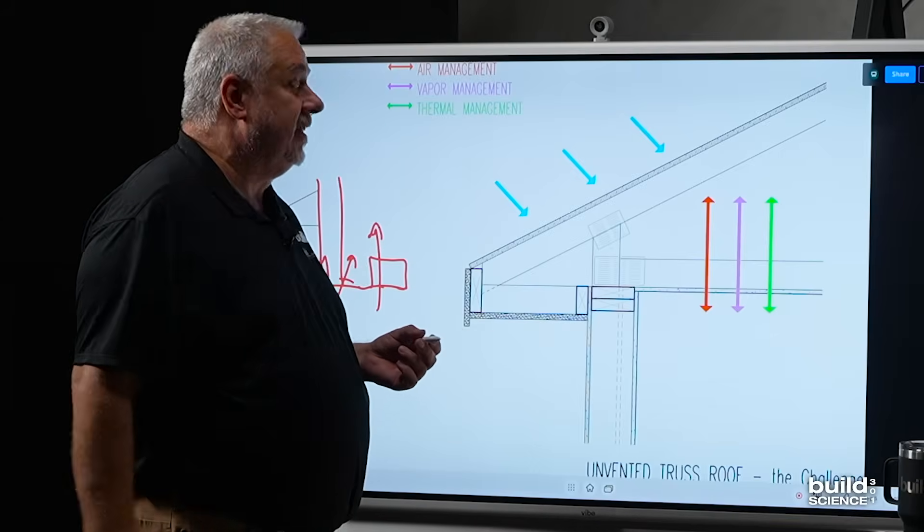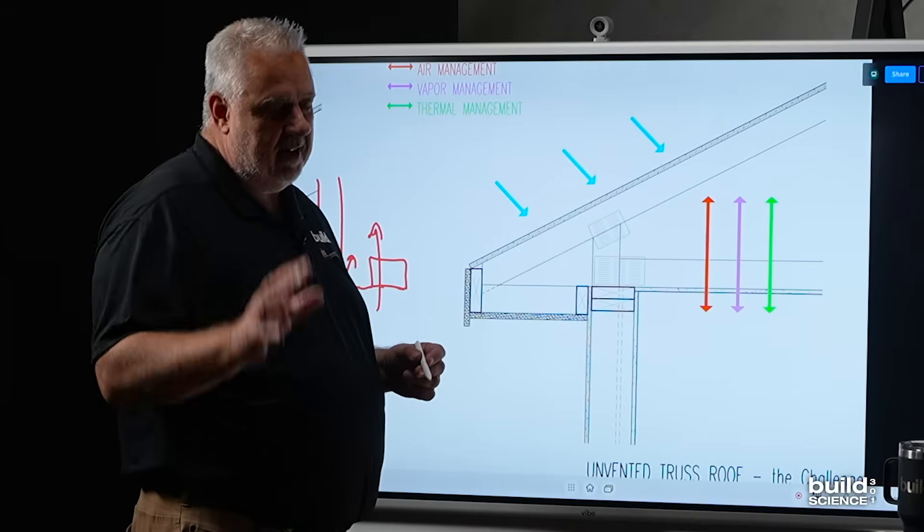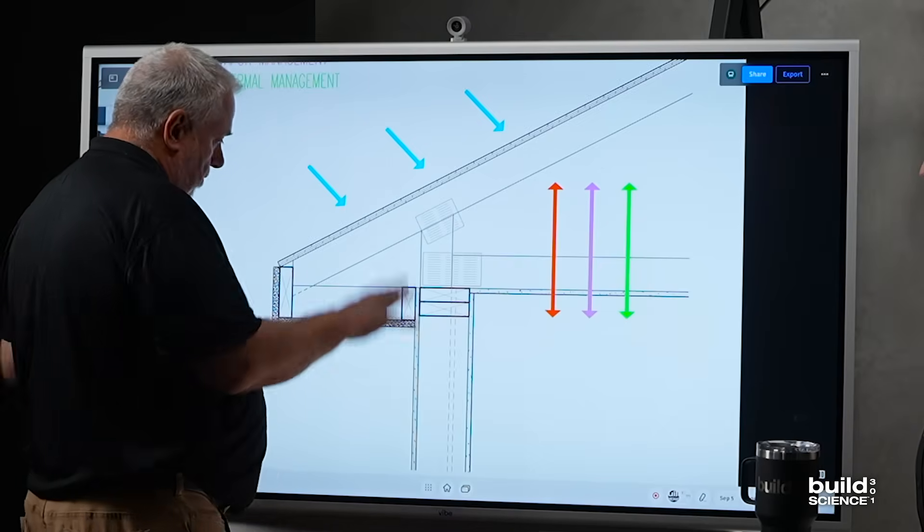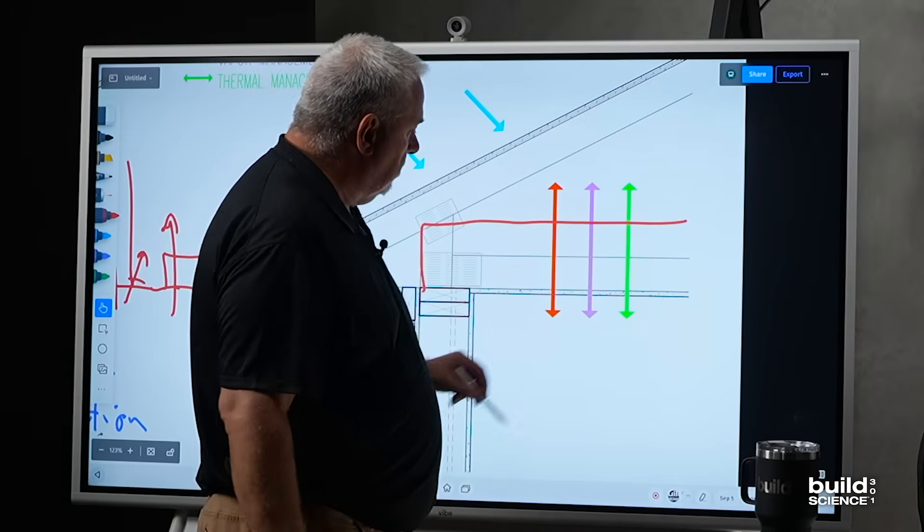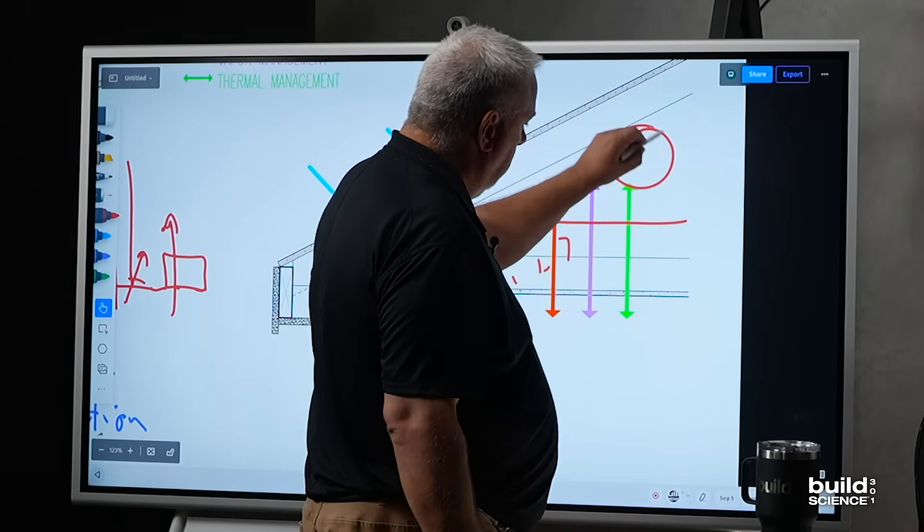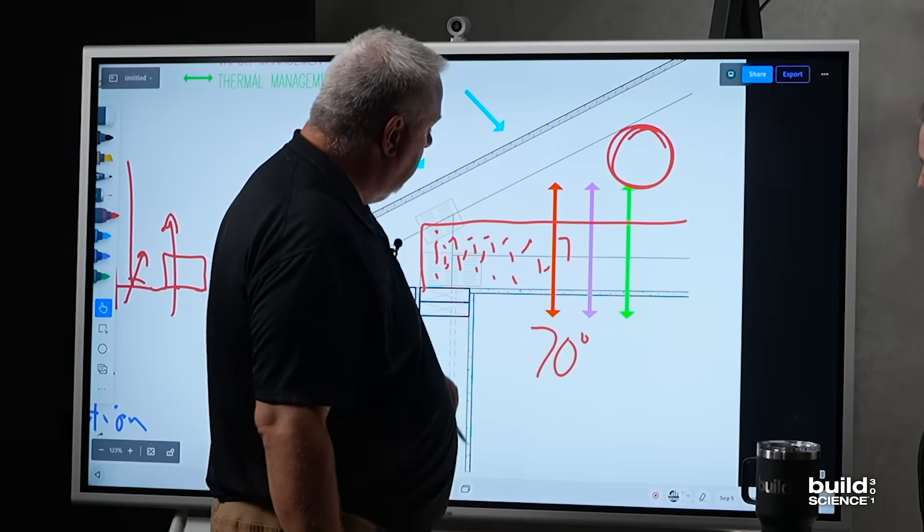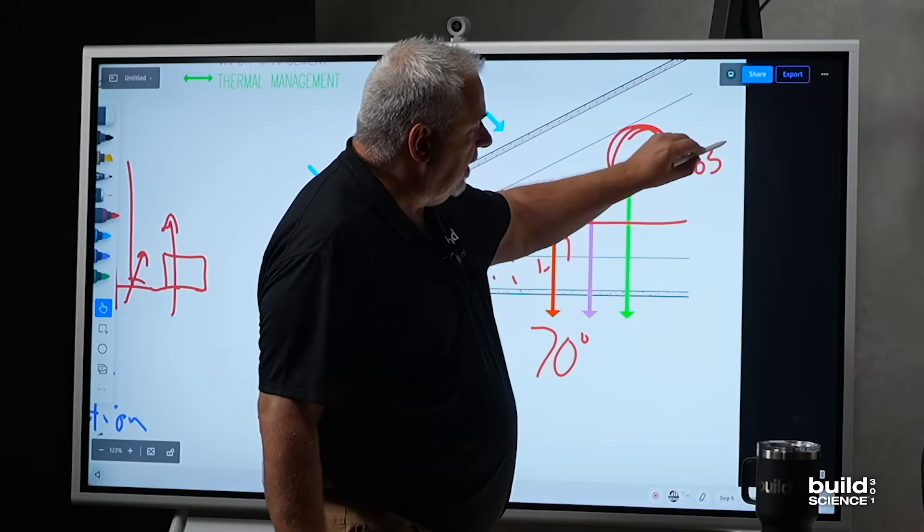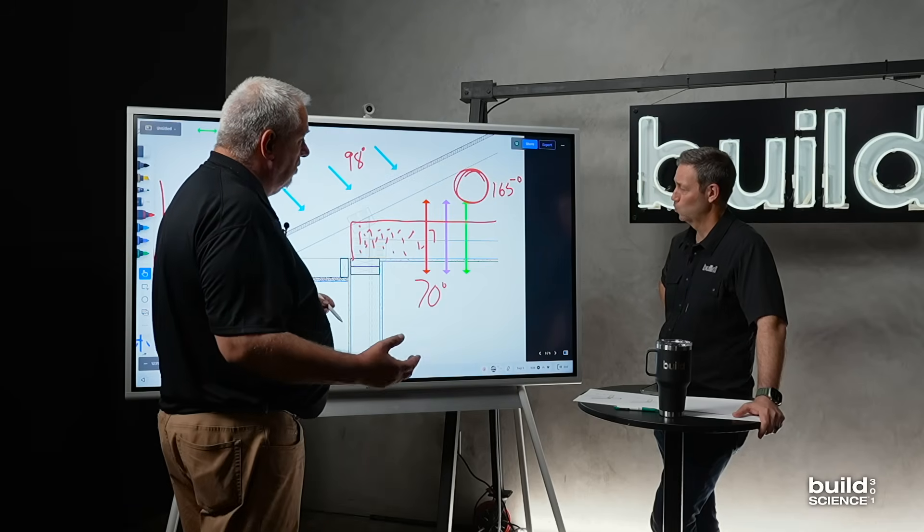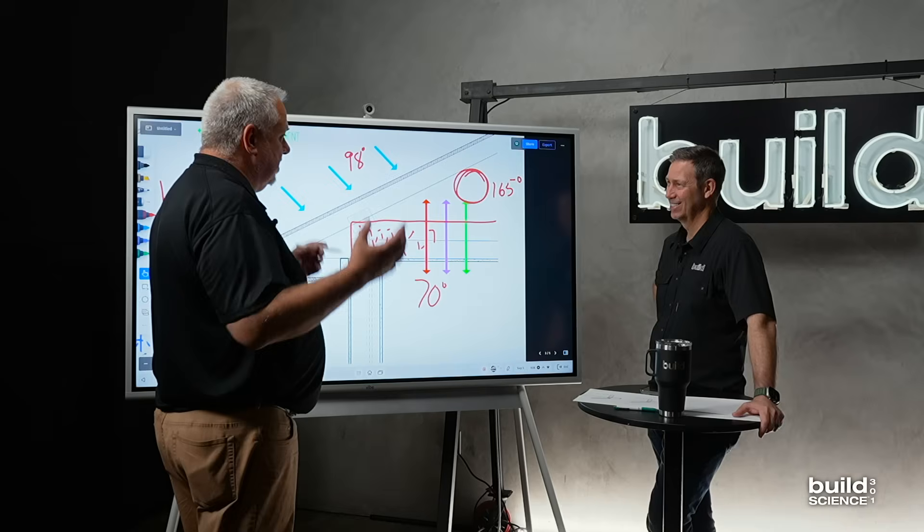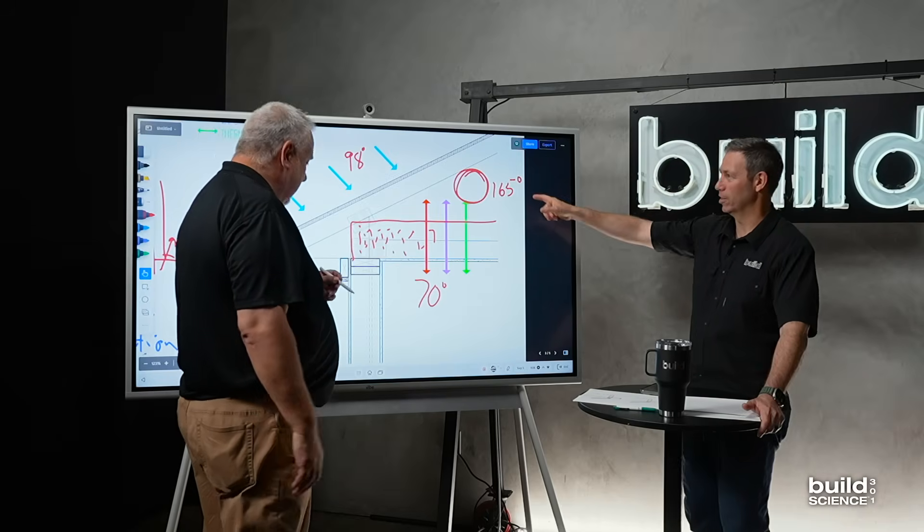I'm going to talk about the idiocy of putting ductwork into a vented attic space. So we have insulation there, and then we'll put a piece of ductwork in here. Houston, 70 degrees here, 98 degrees there. The attic was 165 degrees. We measured it. And it's like if you're up there for five seconds, you're already starting to sweat. That's the beef jerky setting on my dehydrator, 165 degrees.